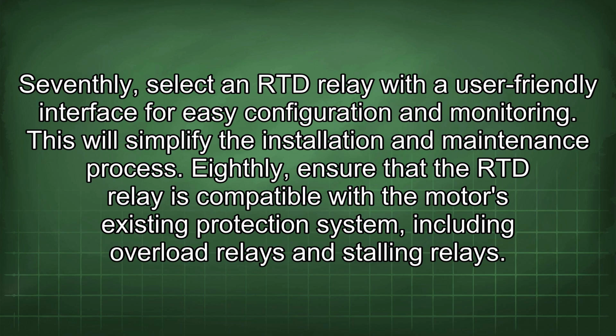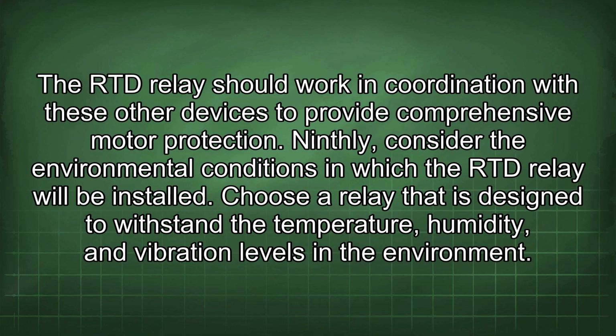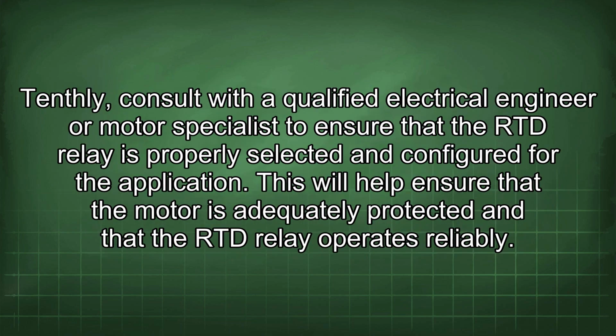Eighthly, ensure that the RTD relay is compatible with the motor's existing protection system, including overload relays and stalling relays. The RTD relay should work in coordination with these other devices to provide comprehensive motor protection. Ninthly, consider the environmental conditions in which the RTD relay will be installed. Choose a relay that is designed to withstand the temperature, humidity, and vibration levels in the environment. Tenthly, consult with a qualified electrical engineer or motor specialist to ensure that the RTD relay is properly selected and configured for the application. This will help ensure that the motor is adequately protected and that the RTD relay operates reliably.